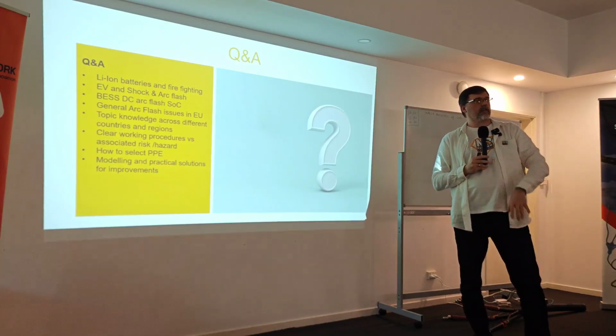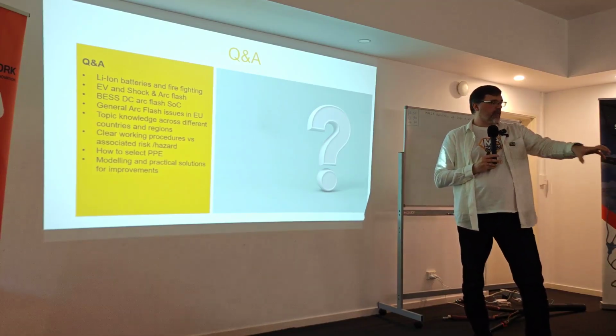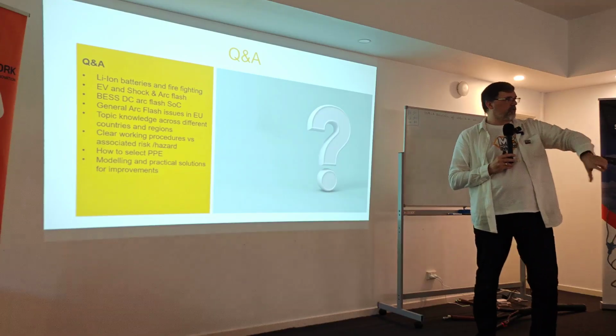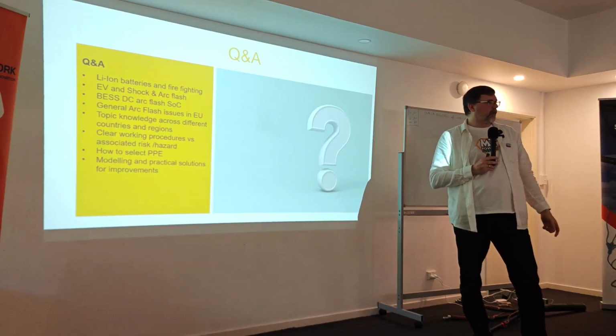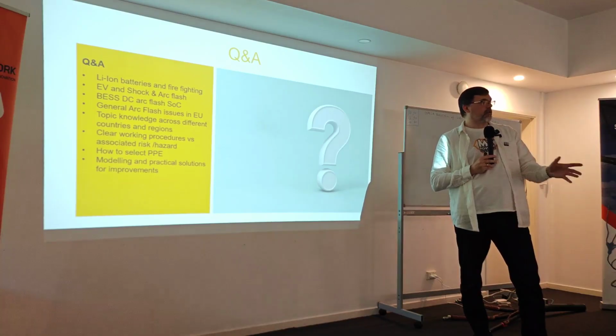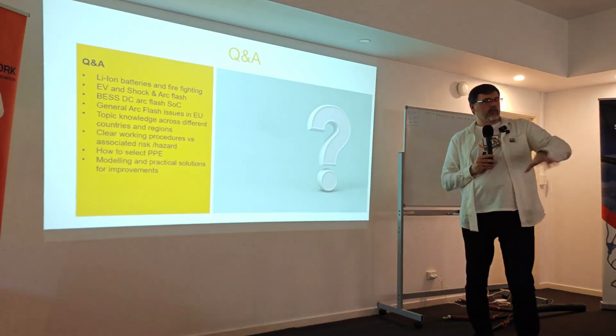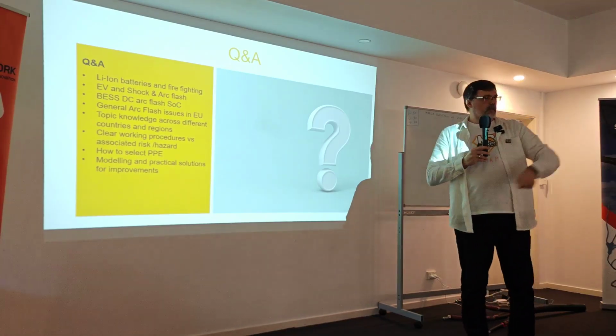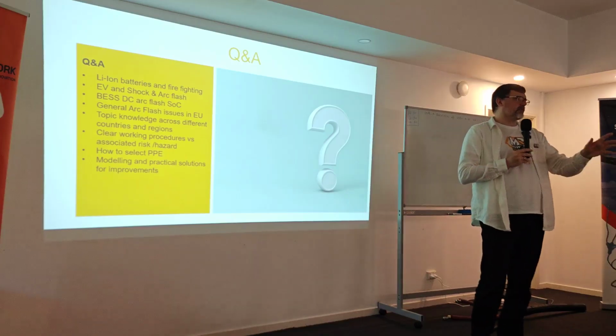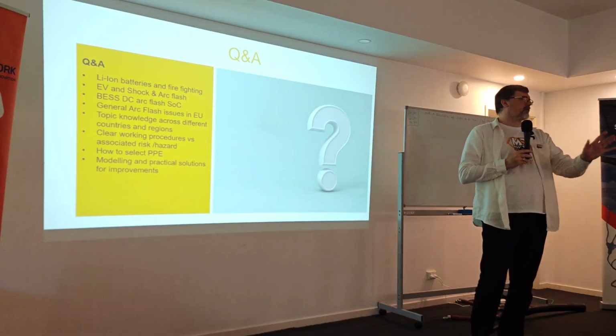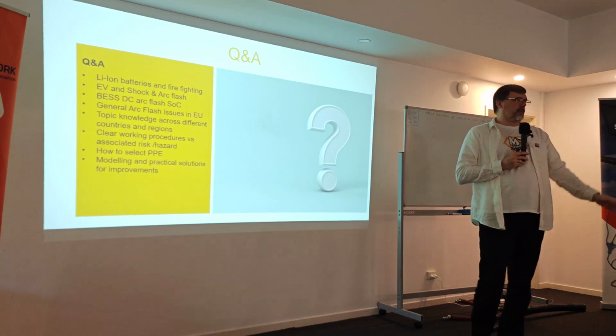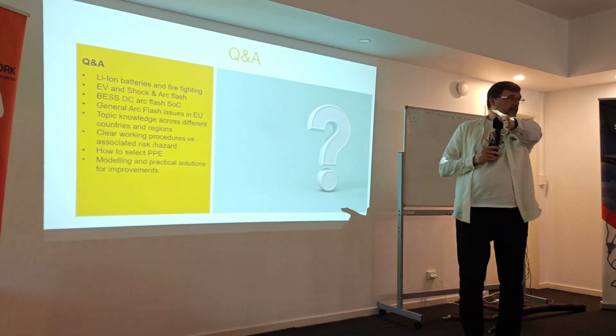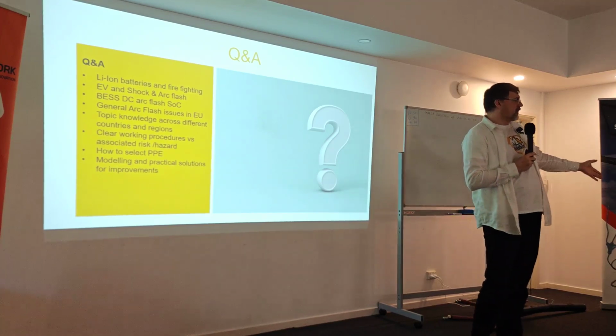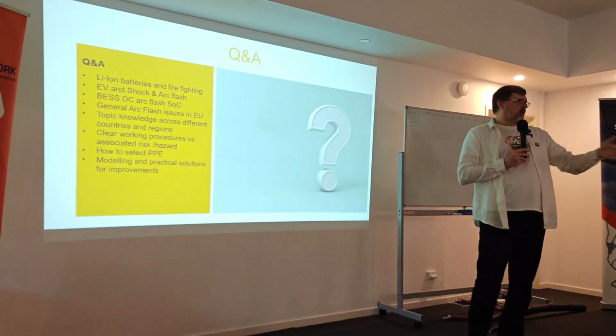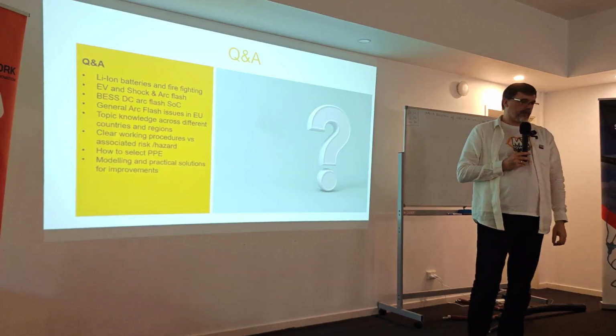We organized the battery itself a bit, so that I split the batteries. There were 2 connections that you can just remove. And they were going below 100 volts, I think 90 volts, through the whole process, and at one step they have to reconnect, and then they didn't have 400, they had like 200-something at the final step. So I said, okay, that's the guy that needs gloves. Everyone else doesn't need the gloves. They will have the arc rated gloves because we were calculating for the arc flash, because that was the problem.